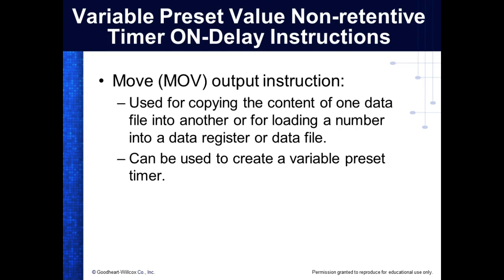So usually we use these multipliers to get times that are not equal numbers of 1. So if I wanted 1.5 seconds, I can't get 1.5 seconds with the 1. So if this was the next one, then I would enter 150, right? And then I would use this multiplier right here, and that would give me a time of what? 1.5.